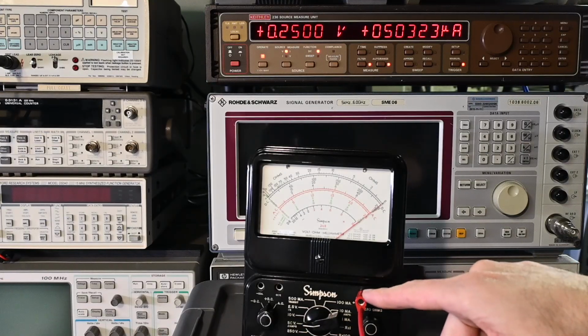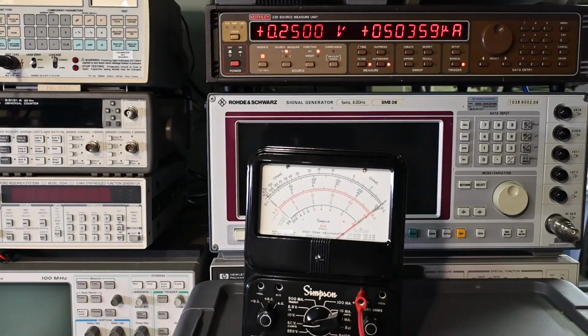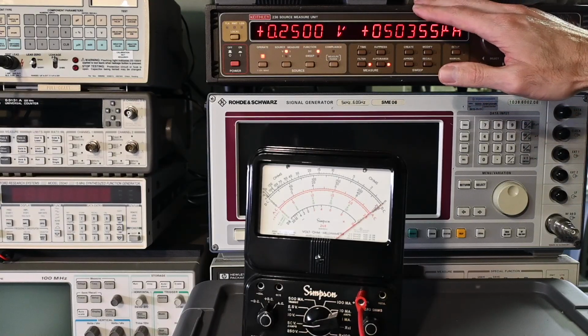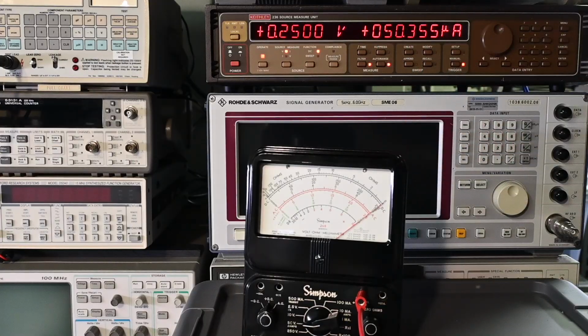So again, when you're using this input, either 50 microamps or 250 millivolts will cause a full-scale indication. And this calibration is extremely critical because all of the DC measurements, and the AC measurements for that matter, rely on this calibration being correct. And the ohm meter functions as well, and the current functions, everything relies on this DC calibration being accurate. So if these first two calibrations are not correct, then the entire meter will not be accurate in any of its measurements. So again, very, very critical, and you want a source like this that's very stable and accurate on these very small values.